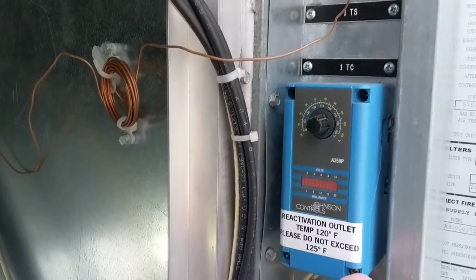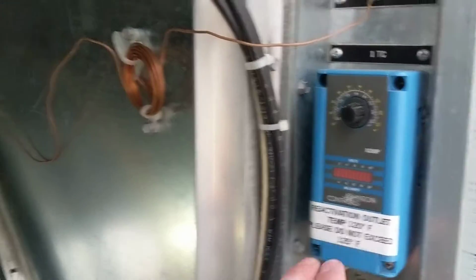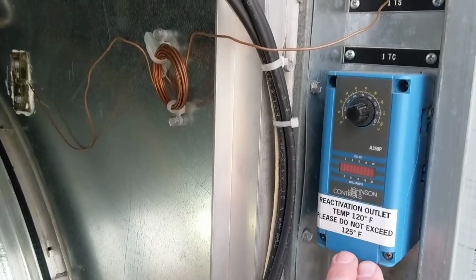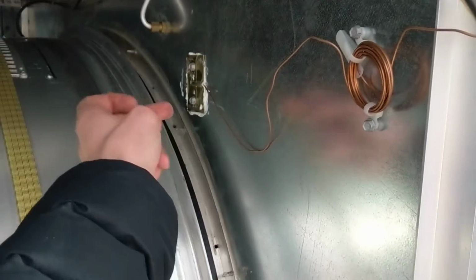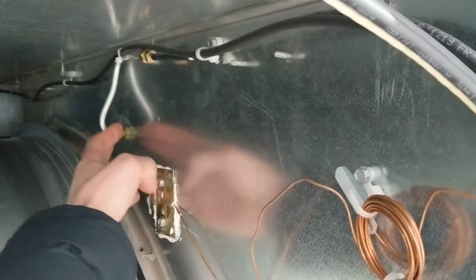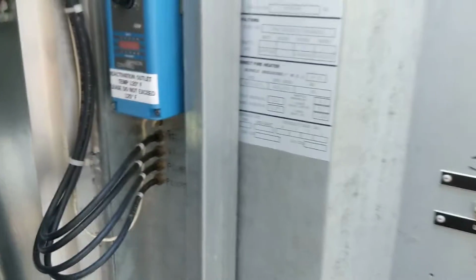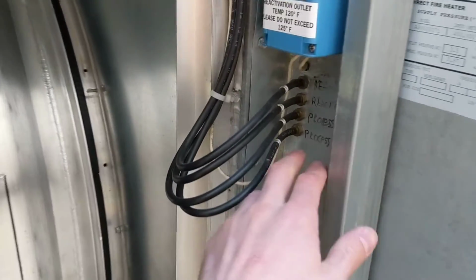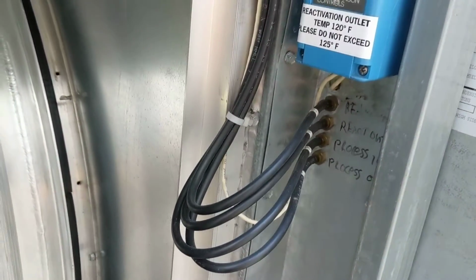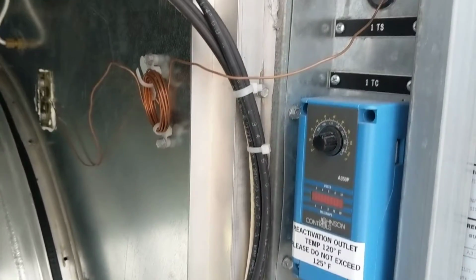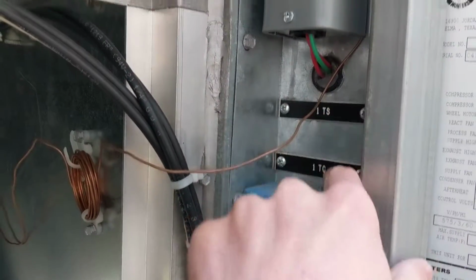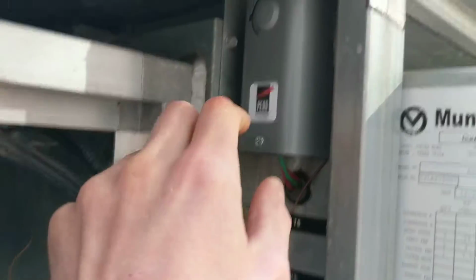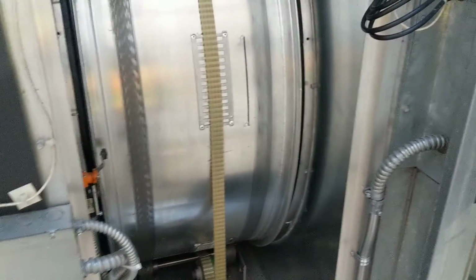Over here, this is reactivation. So this is basically checking the temperature, like you can see where it comes here and it goes through there. It's recording the temperature on the other side of that. Same as this here is measuring the pressure on the other side of that, and you can trace that back to the other side there. And all this stuff is nicely labeled for the most part to help it make it easier to trace issues. Same here, everything's labeled. So TC, TS, you can trace all those back to the wiring diagram. And then there's another one that's around this side.